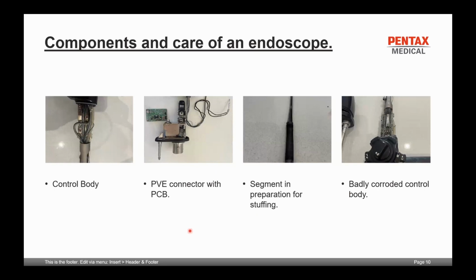Okay, just continuing with the components of the endoscope. So this is a control body of an endoscope. As you can see there, there's quite a few components inside here. You've got your CCD signal wire, you've got a grounding wire, you've got a suction channel, air channel, water channel, light guide fiber bundles, and your remote signal wires as well.